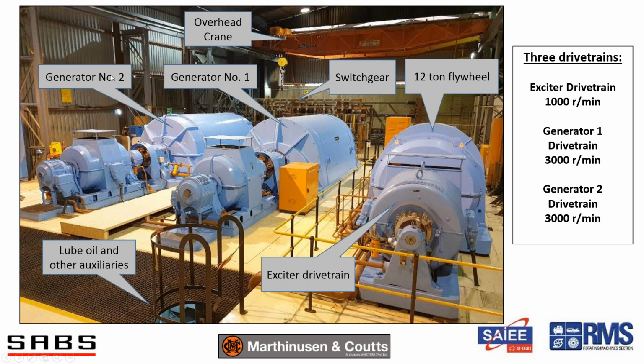So the generators run up with these drive motors here. They are each 1 megawatt, 6.6 kV. They're wound rotor induction motors, so they have big liquid resistor starters to allow them to run up. Now, a modern plant like this would probably use variable speed drives and squirrel cage induction motors, but these work very well, and they are very unusual in that they are 2-pole 3000 RPM wound rotor induction motors, for the rotating machine specialists out there. Then the excitation drivetrain. This drivetrain includes another drive motor, 800 kilowatts, also 6.6 kV. This drivetrain is 1000 RPM. It drives 2 DC generators with a 12-ton flywheel between them. And the 2 DC generators power the fields of the 2 generators. And the flywheel is there to overcome the armature reaction.